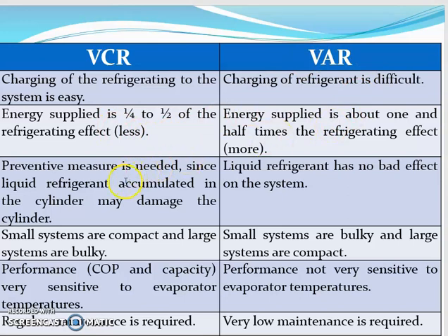In case of VCR system, a preventive measure is needed since liquid refrigerant accumulated in the cylinder may damage the cylinder, but in case of VAR system, liquid refrigerant has no bad effect on the system. In case of VCR system, small VCR systems are compact and large VCR systems are bulky, but it is the opposite in case of VAR. Small VAR systems are bulky and large VAR systems are compact.